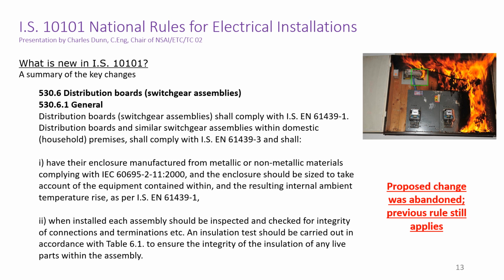And what is non-combustible anyway? Does that mean inflammable at 70 degrees Celsius, or at 800 degrees Celsius, or maybe at 90 degrees Celsius for 3 hours? There was really no point in trying to establish a new standard here.